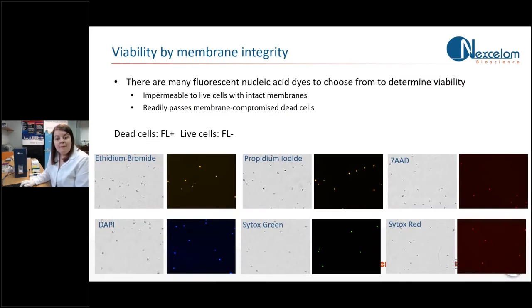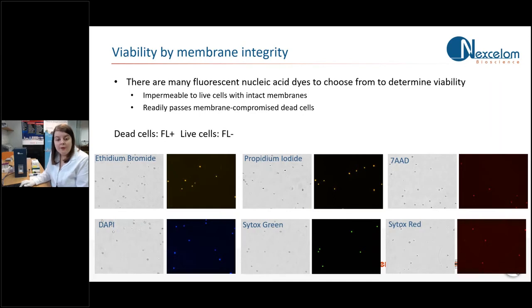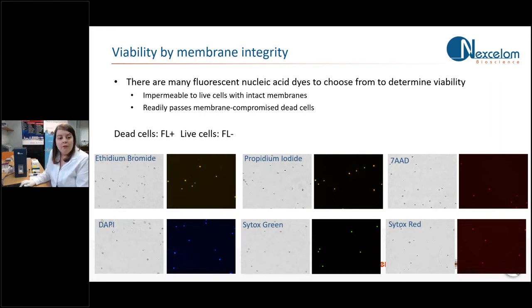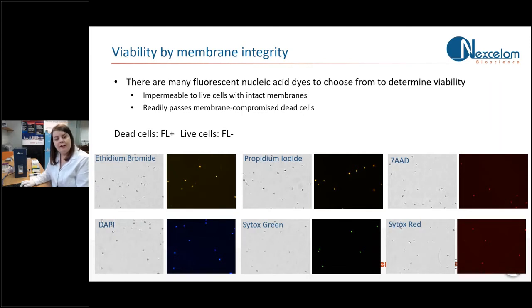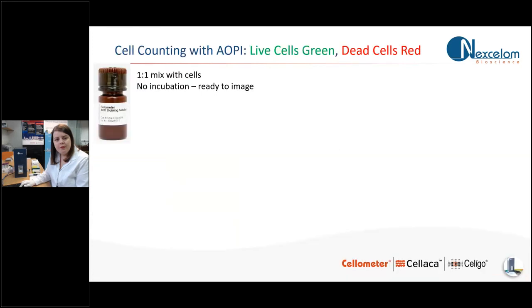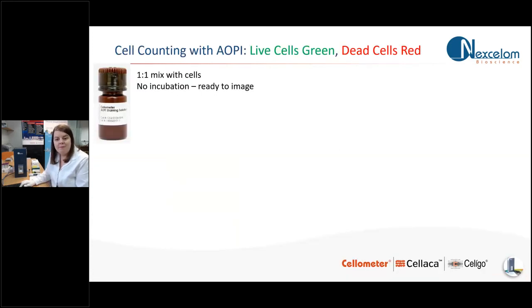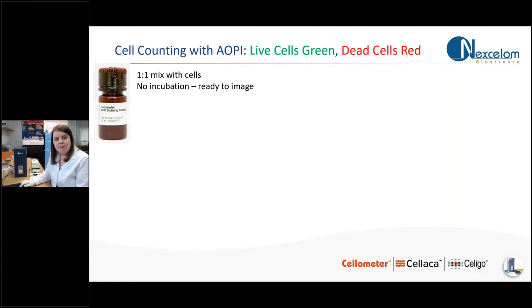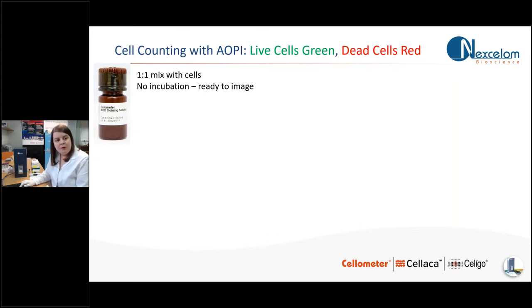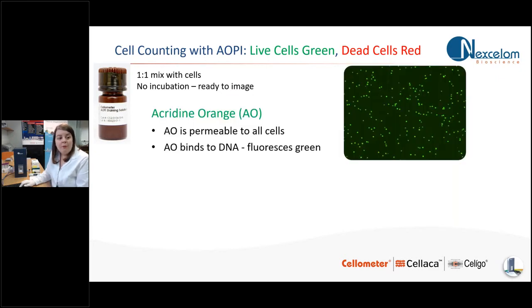So when it comes to viability, there are many methods for detecting live and dead cells, right from trypan blue to various different fluorescent reagents, all of which we can use on the Spectrum. And we have a few examples of images here and the different dyes you can use. But by far, one of the most accurate and easy and robust methods for assessing the viability of your cells is to use acridine orange and propidium iodide. So these two dyes come as a pre-mixed vial and you simply mix them one-to-one with your cells. There's no incubation time and they're ready to image.